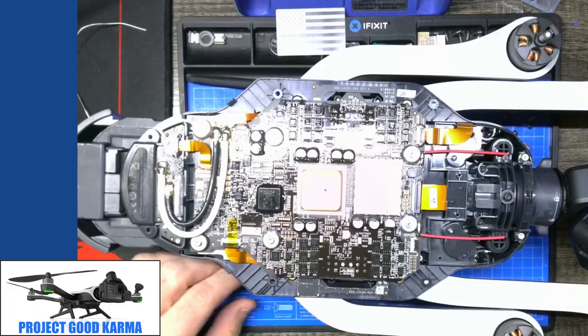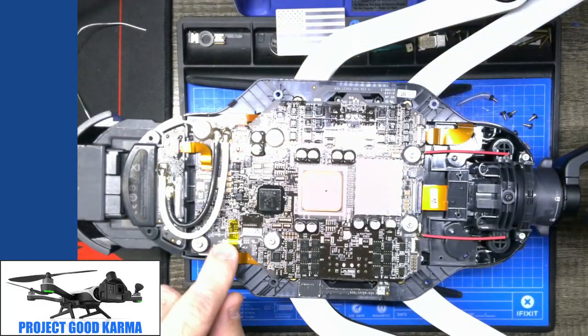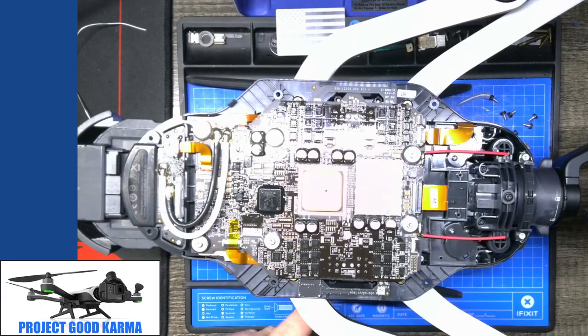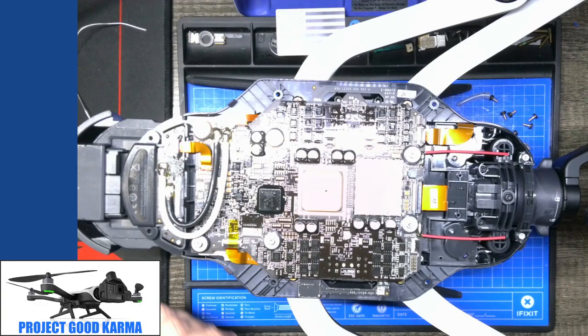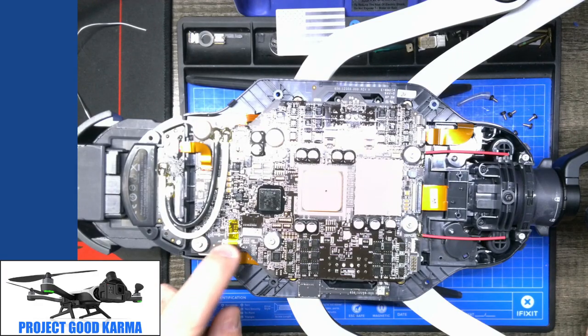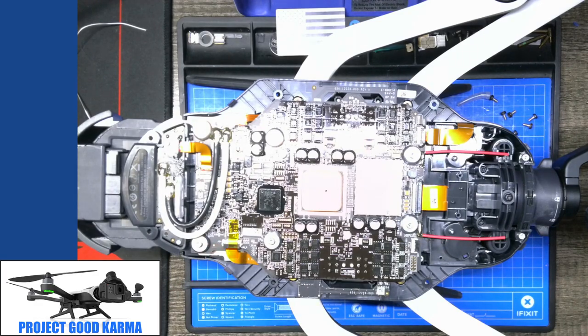I normally test all this before I box it up. I'm going to put the cover back just in case. It's pretty commonplace that if you don't get this cable seated properly, you'll have an error message on the screen that says something to the effect of please extend the arms, and that will be 9 times out of 10 because of this guy. If it's not this guy, then there's damage to one of the micro switches or maybe the cam on the arm.